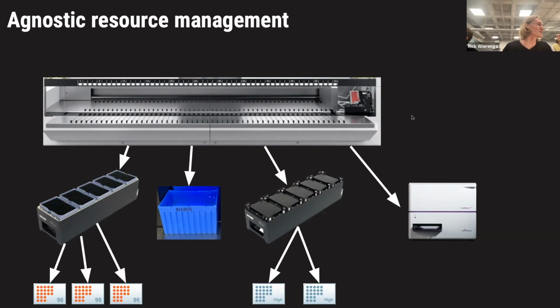We sort of view this model of resources as a tree where the deck is the root of the tree, which contains many child resources, if you will, which can be carriers, just the blue bucket, plate carriers, or a plate reader. And then for the tip carrier, for example, it contains tip racks, which you can see on the bottom here, or plates in the case of a plate carrier, as their respective children.